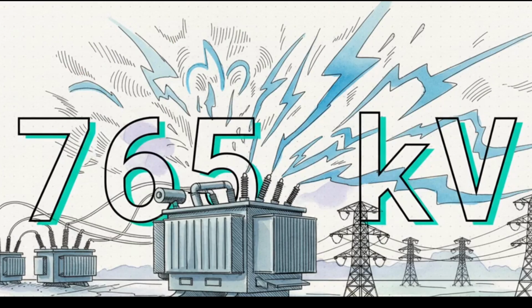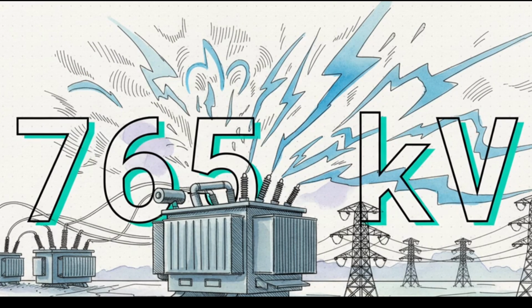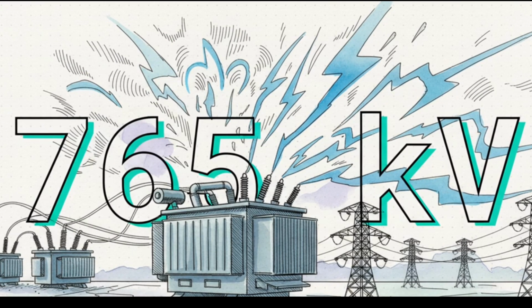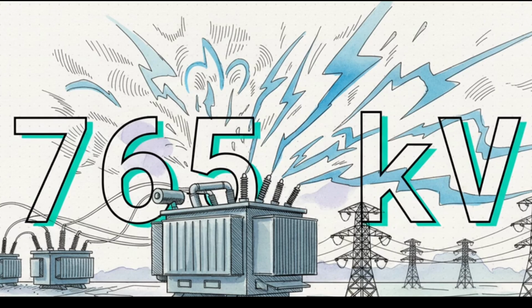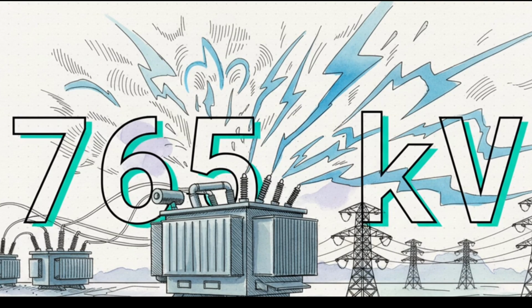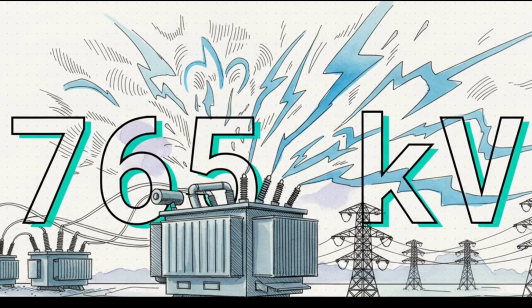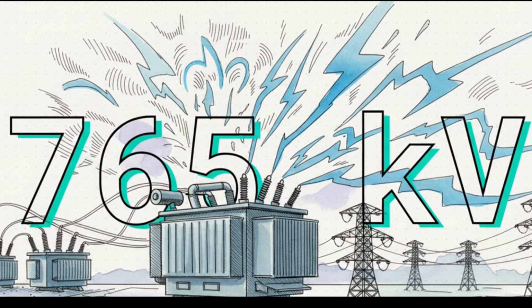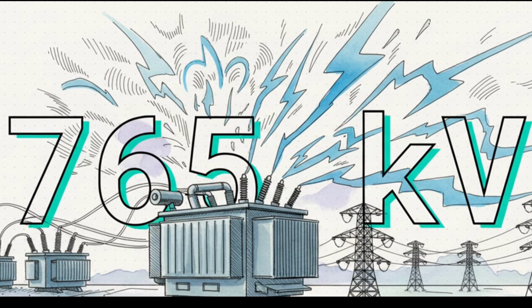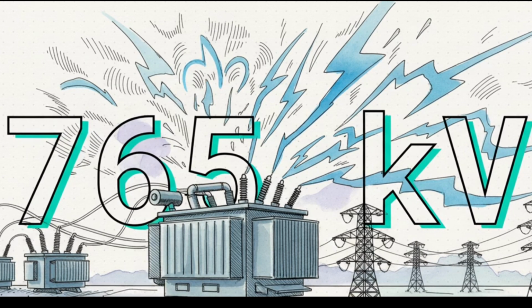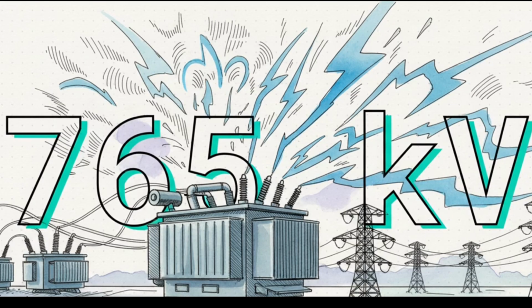You simply can't generate power at a million volts right out of the gate without destroying the equipment. But for long-distance primary transmission, moving power across entire states or vast regions, that starting voltage has to be massively stepped up. Using transformers, the grid pushes this voltage from 11 or 25 kilovolts up to 220, 400, or even an astonishing 765 kilovolts for primary transmission.